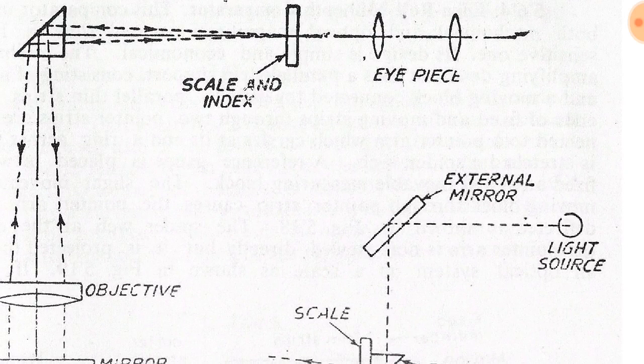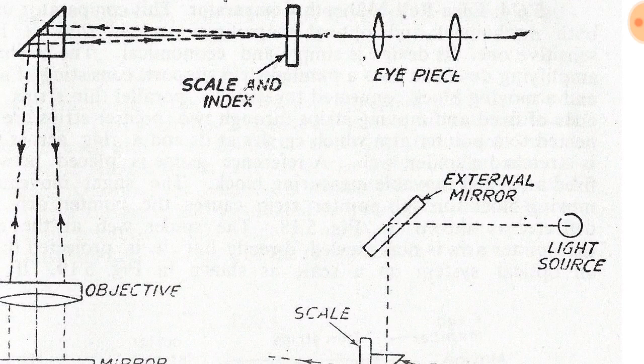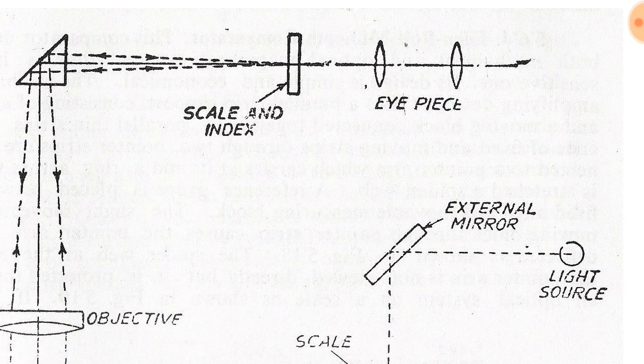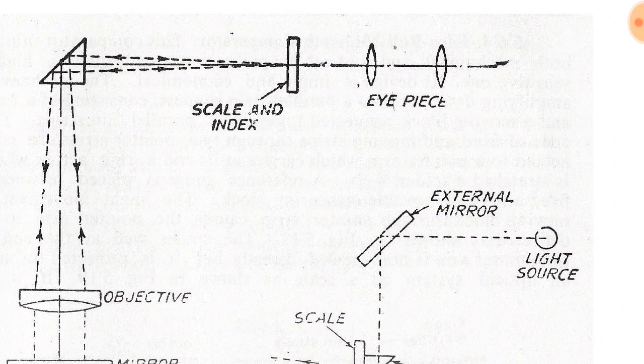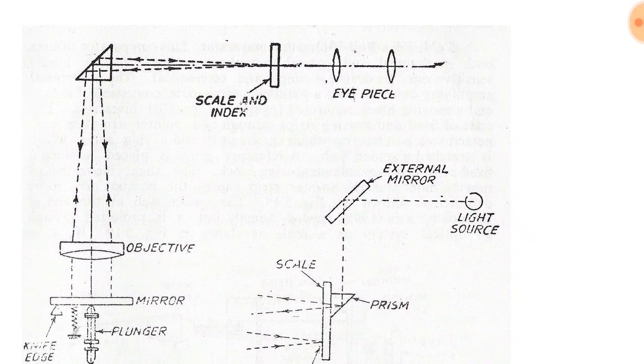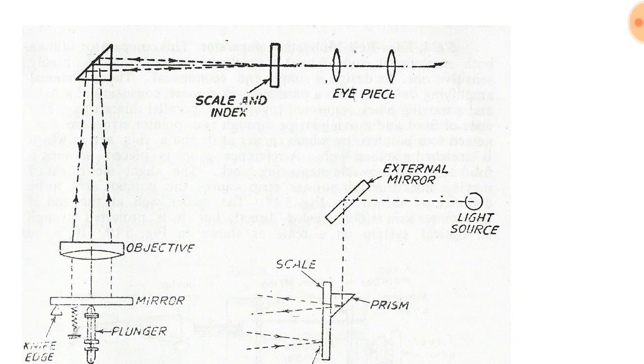With the eye placed near the eyepiece, a fine reference or index is provided, and the system of lenses is arranged so that the image of the scale is projected in the same focal plane. Thus, with the movement of the scale, the image can be measured with reference to the fixed line. The division of the scale image opposite to the index line indicates the amount of movement of the contact plunger.